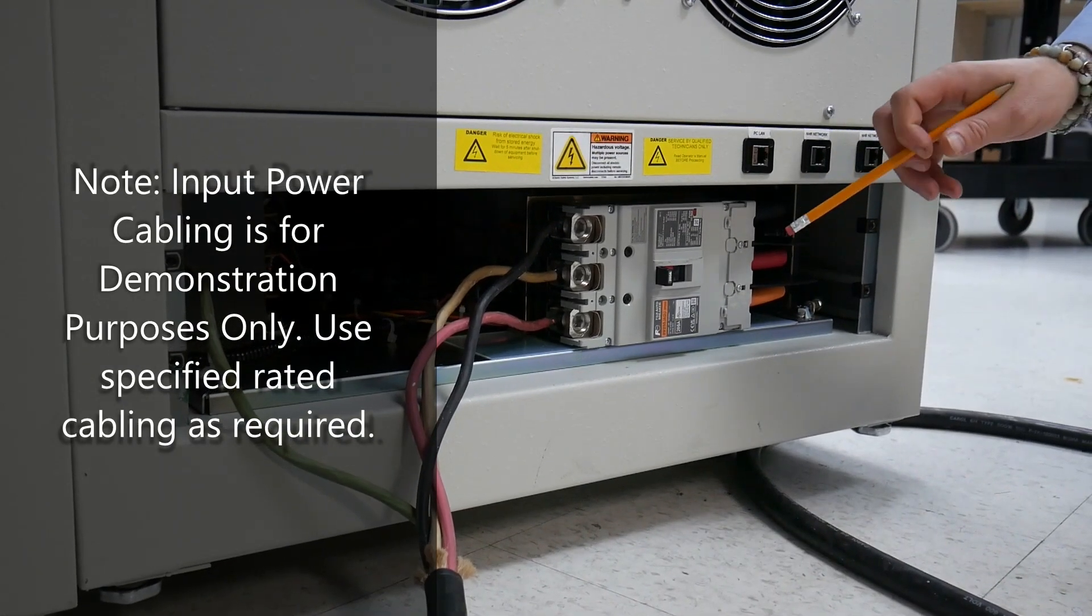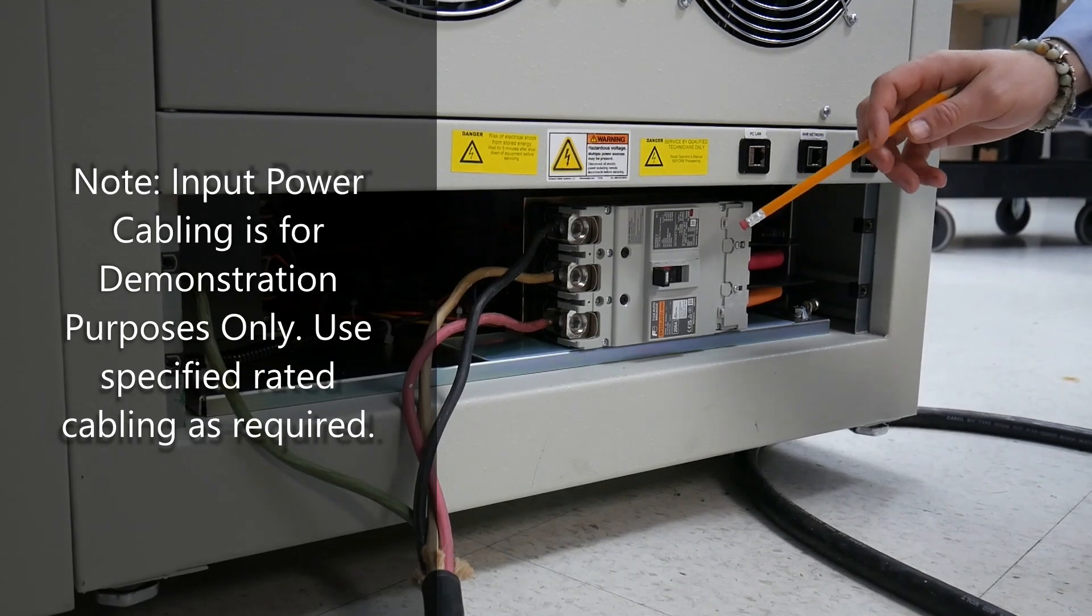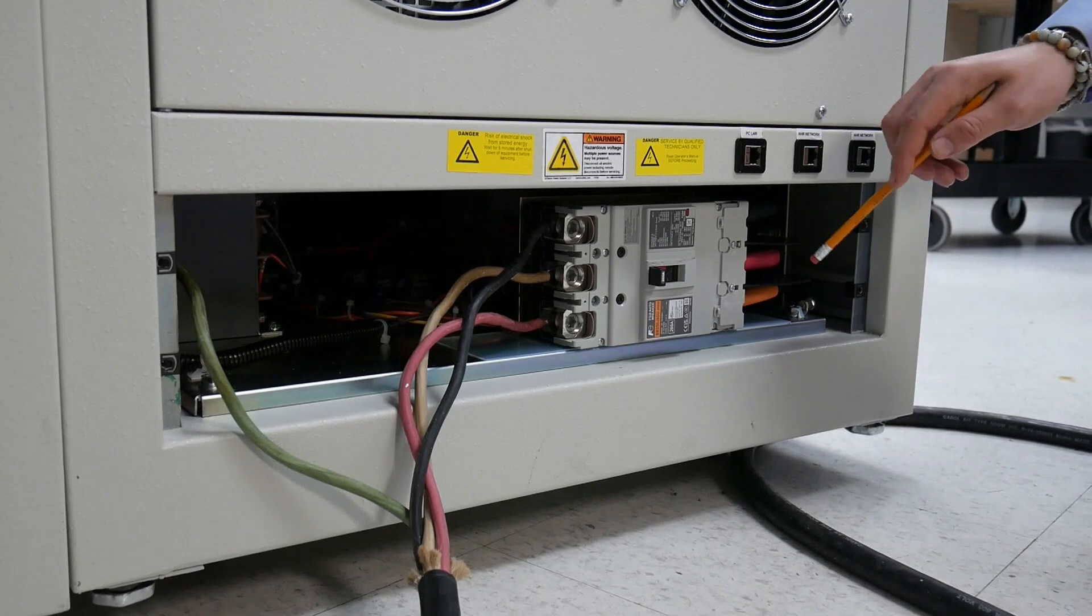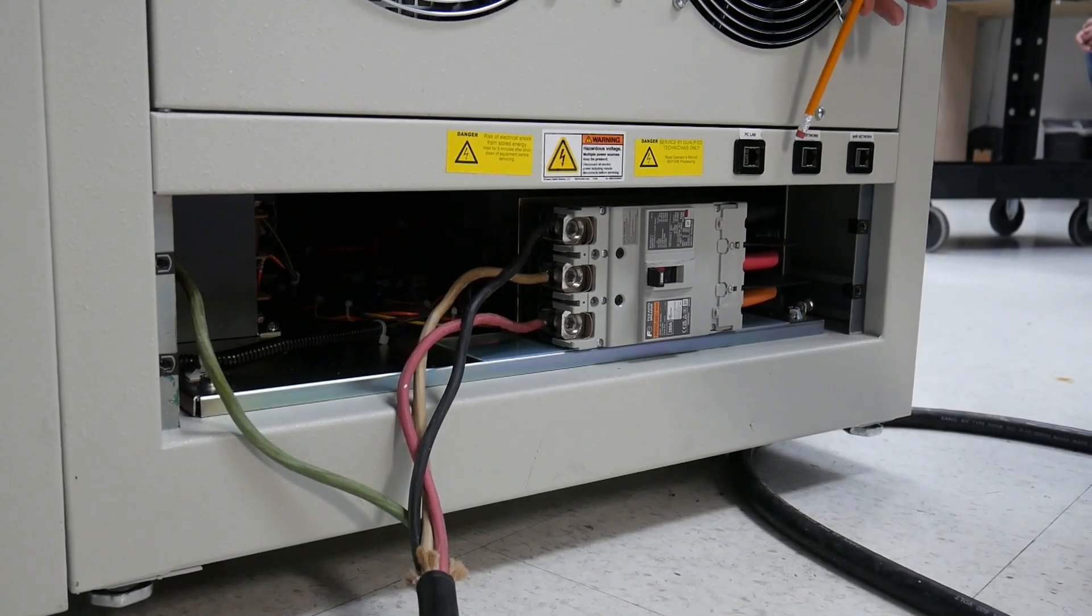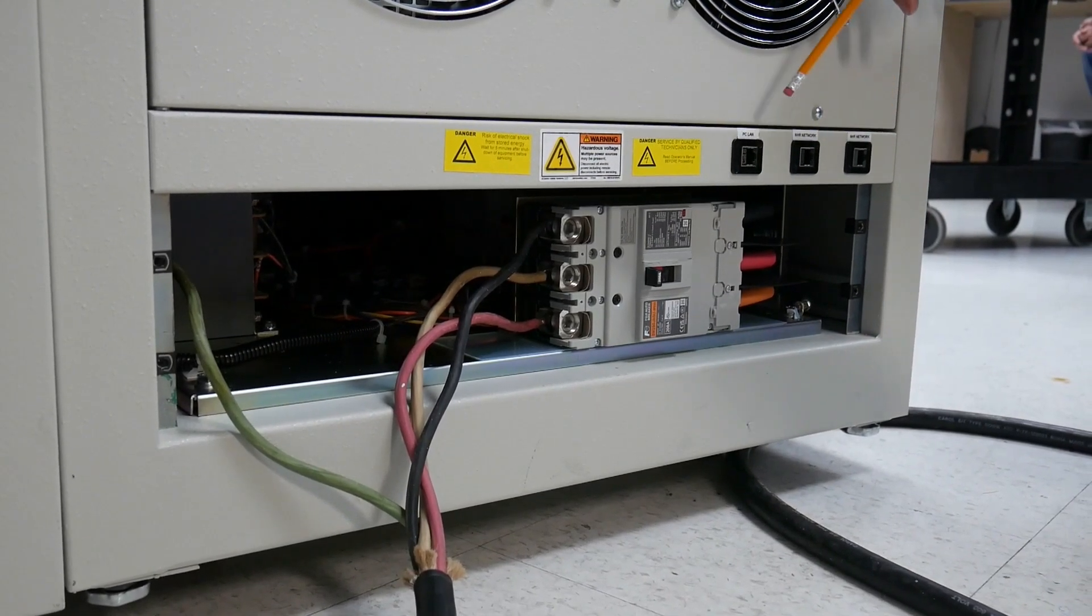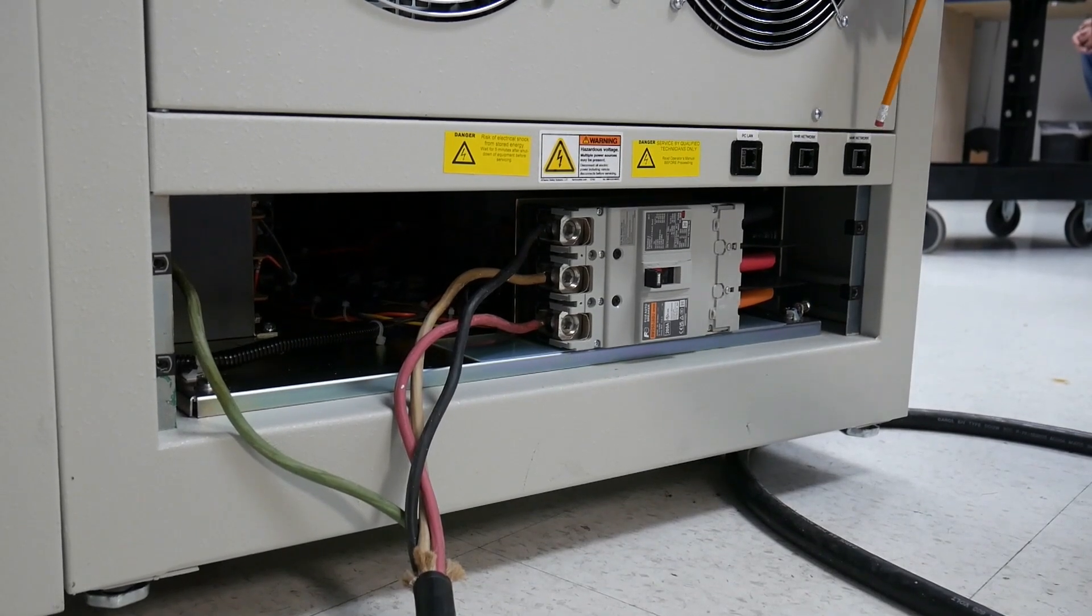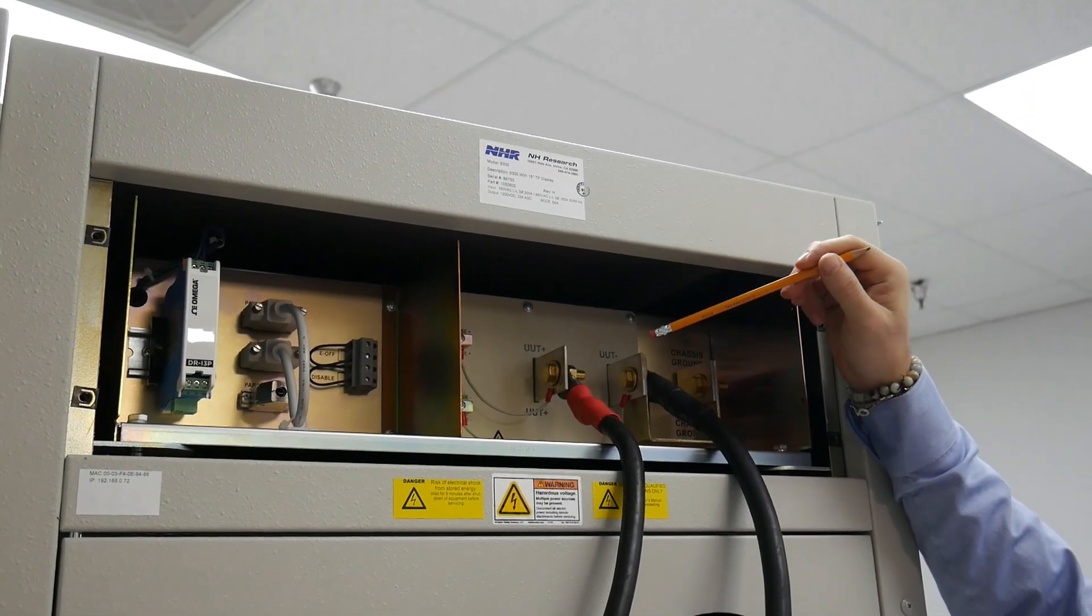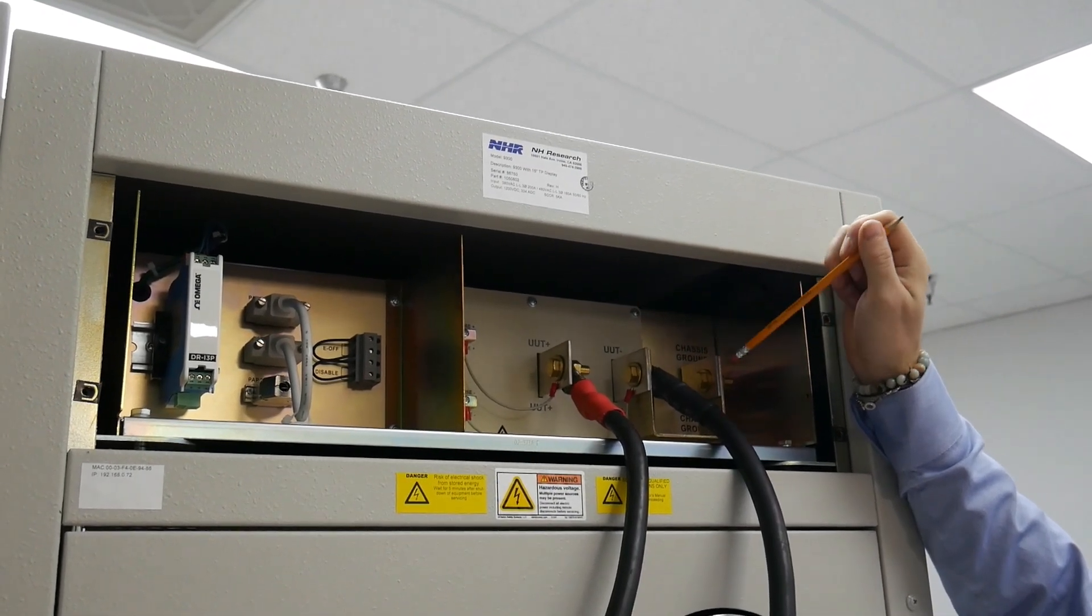Your first step is to come over to the back of the unit. Below you have your AC three-phase input connections as well as your ethernet communication ports to parallel the units and plug them into your software. At the top you have your DC UUT output ports.